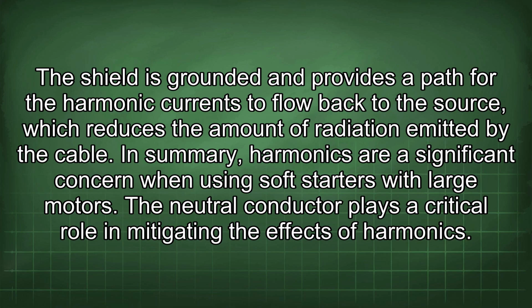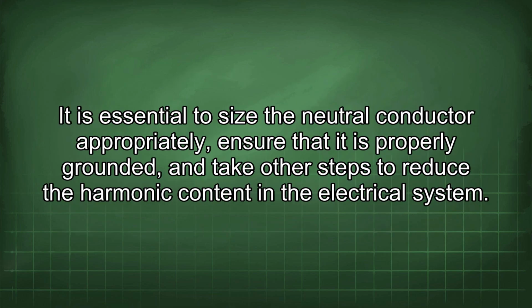In summary, harmonics are a significant concern when using soft starters with large motors. The neutral conductor plays a critical role in mitigating the effects of harmonics. It is essential to size the neutral conductor appropriately, ensure that it is properly grounded, and take other steps to reduce the harmonic content in the electrical system.